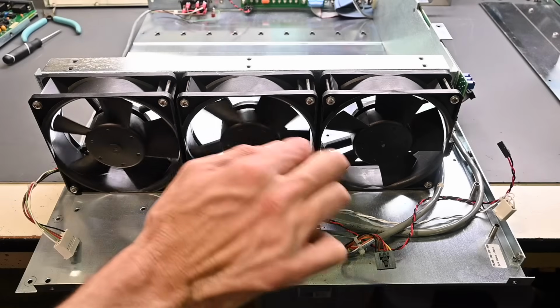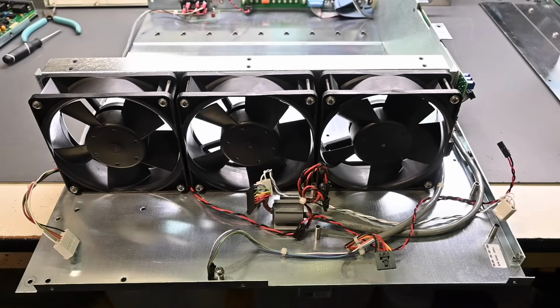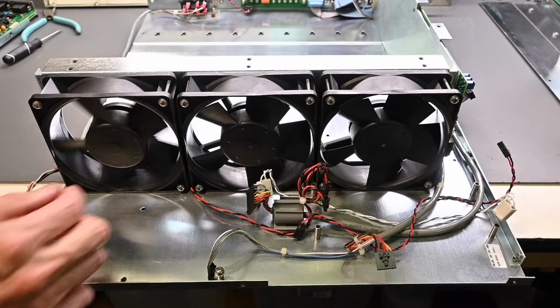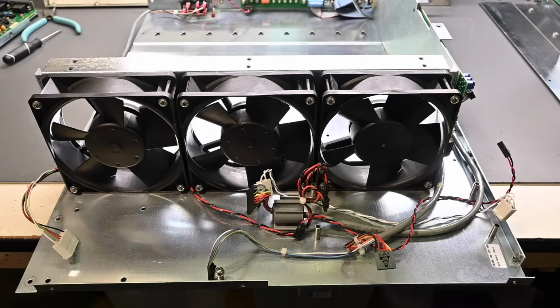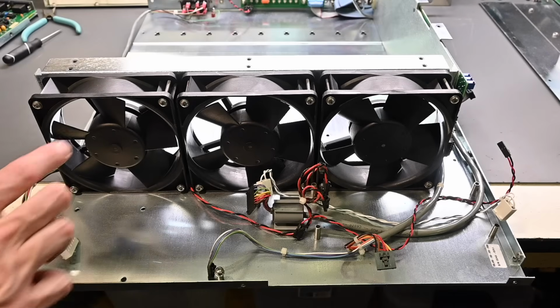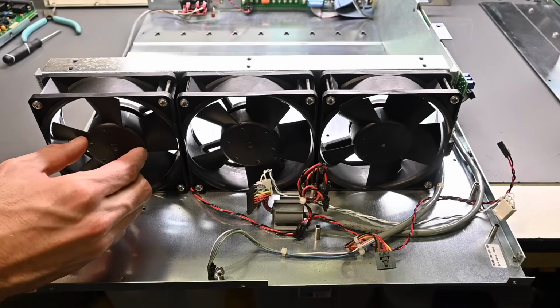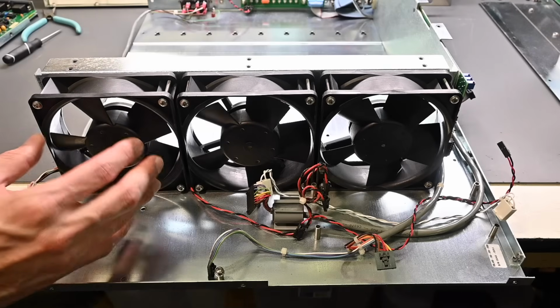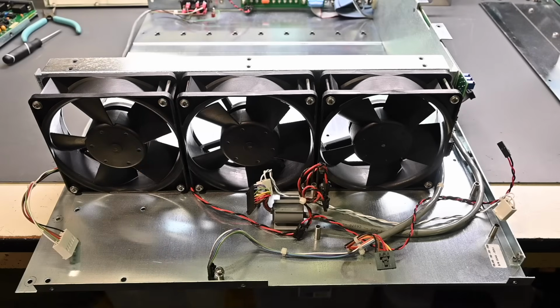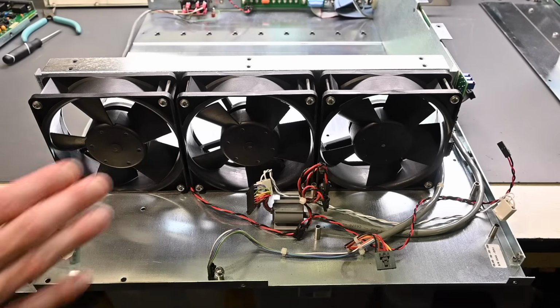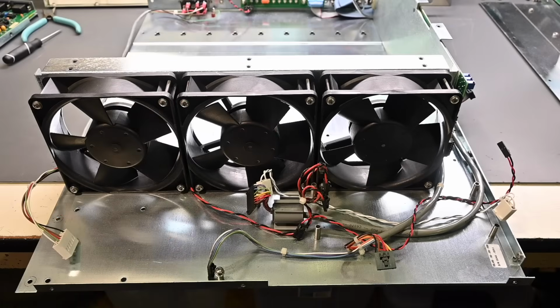And the fan motors are in good condition, so they spin very easily. You can see how they rock back and forth, and that's always a good sign. So the magnetism in the motor is able to rock just a little bit when they stop. It means that the bearings turn very freely. So if you spin a fan motor like this, and they just come to a stop and they don't want to rock back and forth, kind of a stiff feel, it means the bearings are on their way out. So these were extremely dusty and dirty. That's all been cleaned up.